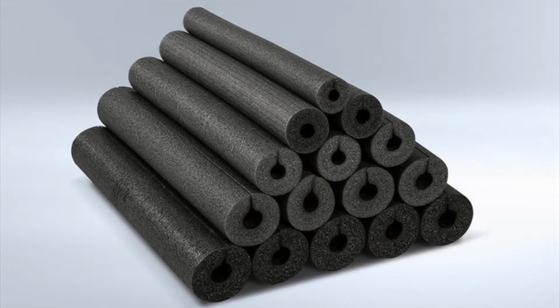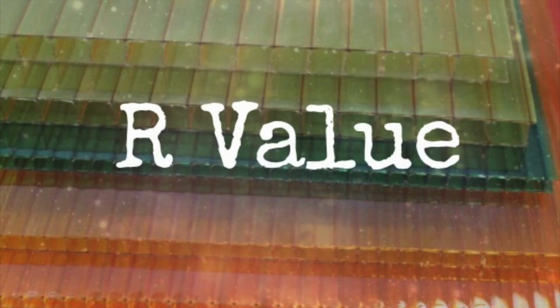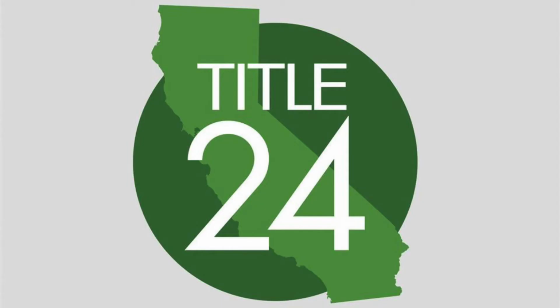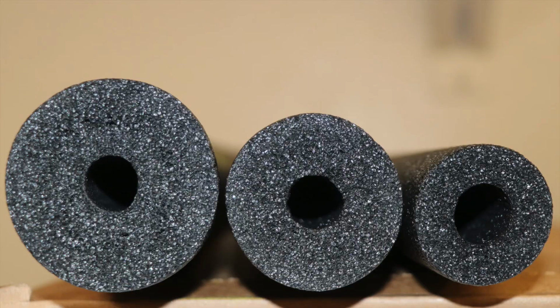You might ask yourself, why are there so many different sizes and shapes? Insulation is rated in R value, the capacity of an insulating material to resist heat flow. The higher the R value, the greater the insulating power. By code in California, there's a minimum R value of 4 in Title 24. Let me give you some examples of how wall thickness equals R value.